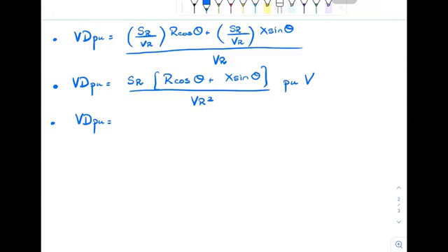So you know that capital R is equal to small r into L, but instead of writing this, we are going to write it like this, because this will later be replaced in terms of L by multiplication with a suitable factor, either 2 by 3, 1 by 2 or 1. So the selection of this factor will be according to the nature of load density.